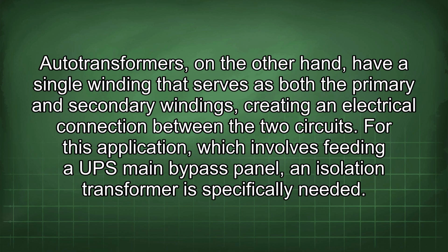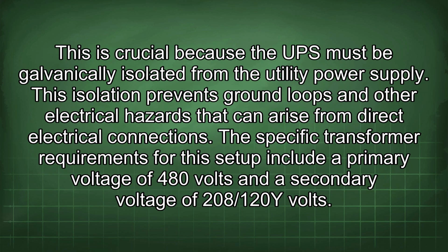For this application, which involves feeding a UPS main bypass panel, an isolation transformer is specifically needed. This is crucial because the UPS must be galvanically isolated from the utility power supply. This isolation prevents ground loops and other electrical hazards that can arise from direct electrical connections.